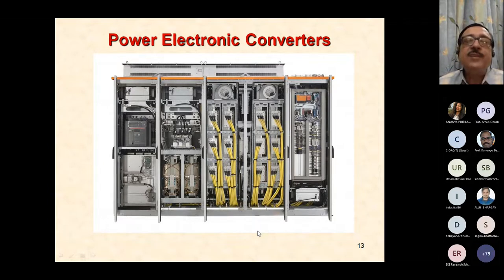So whenever we teach the students, we say a three-phase rectifier produces an output ripple which is 6 times the input supply frequency. That's true only when the supply voltages are balanced. The moment you have one voltage which is larger than the others, you'll see that peak coming in at the output at a higher magnitude, and so a 100 hertz ripple comes in at the output of a 300 hertz, three-phase rectifier. So you have these problems in real life, which we have to tackle.